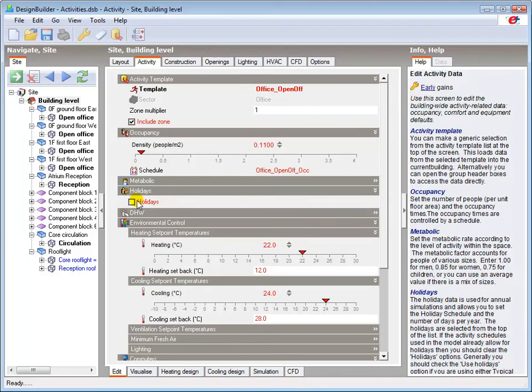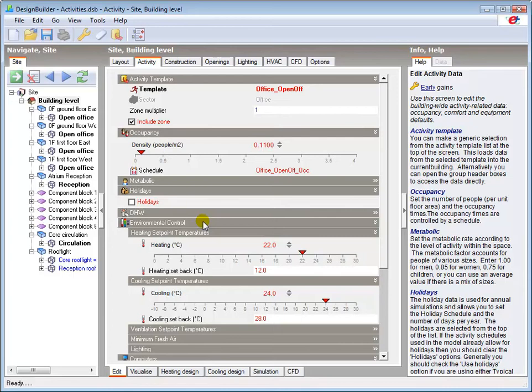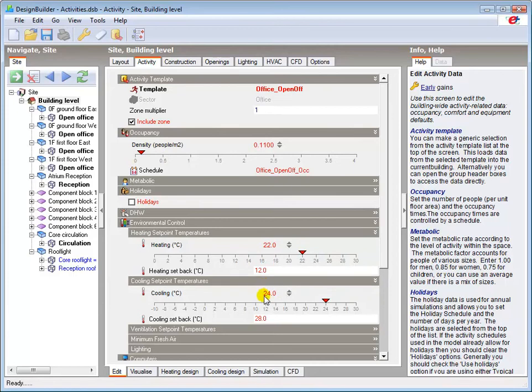The Environmental Control options dictate the operational set points for each of the systems when those systems are scheduled on. For example, the default model data with the OpenOffice template loaded will control the heating to 22 degrees C, and switch on mechanical cooling above 24 degrees C.